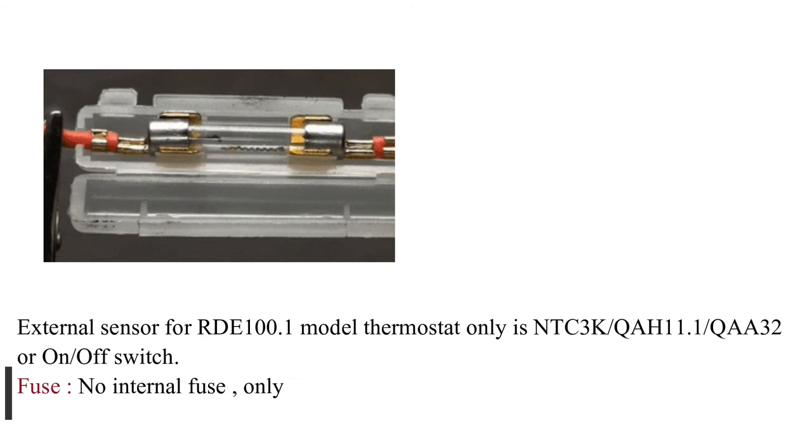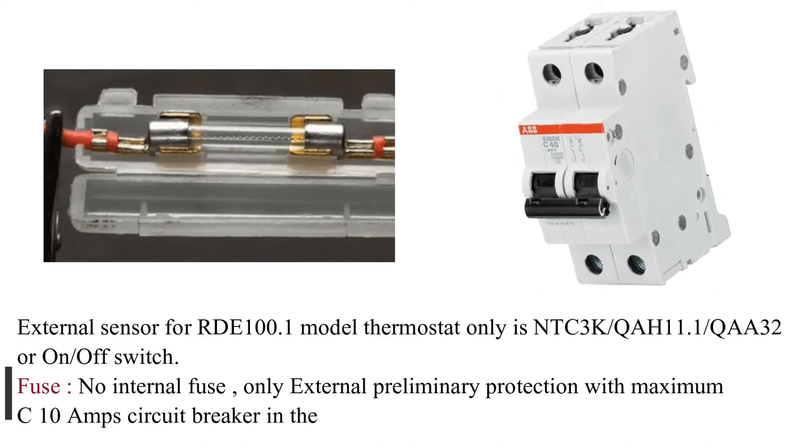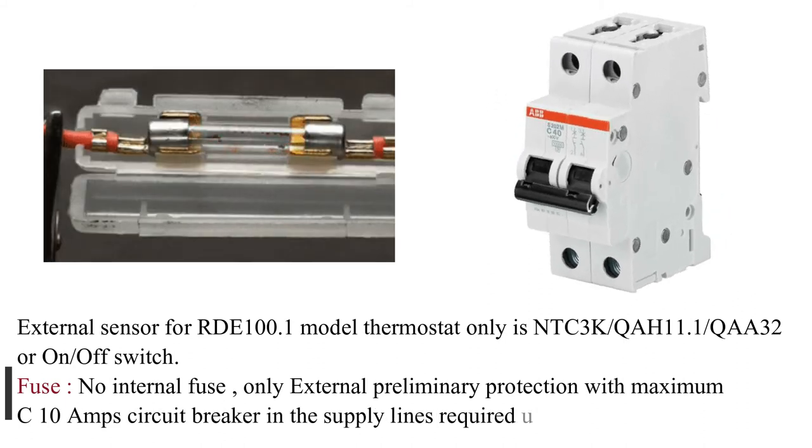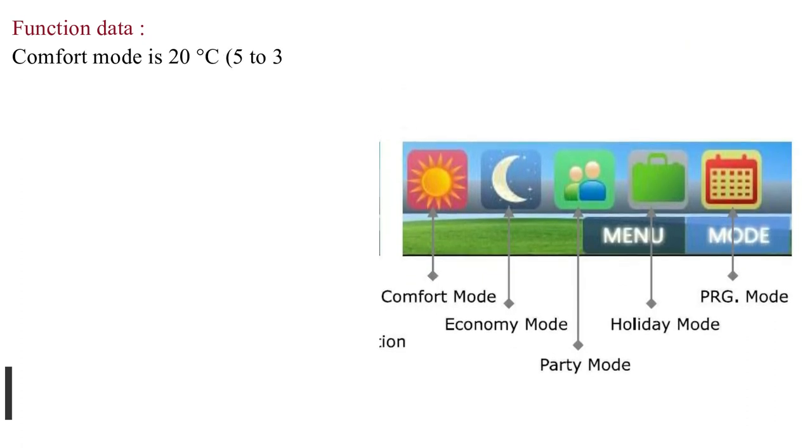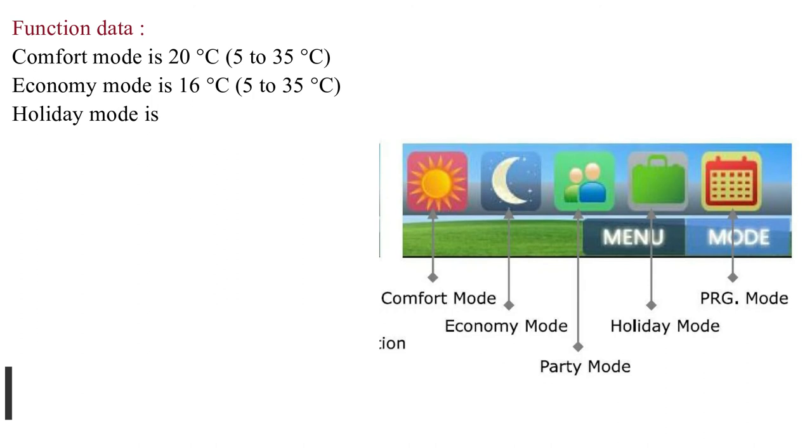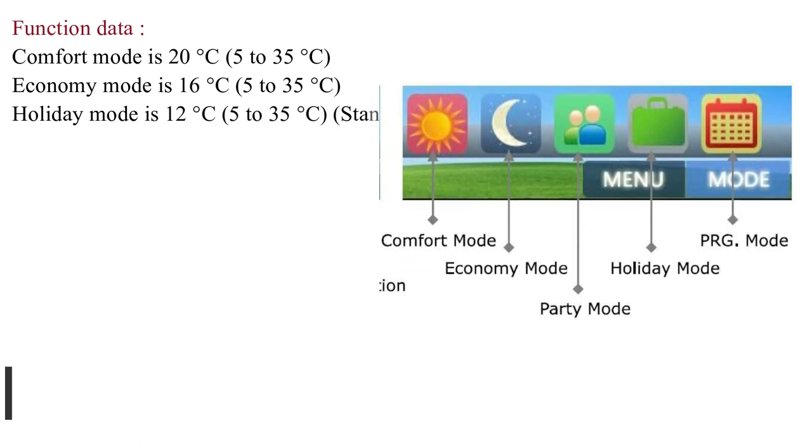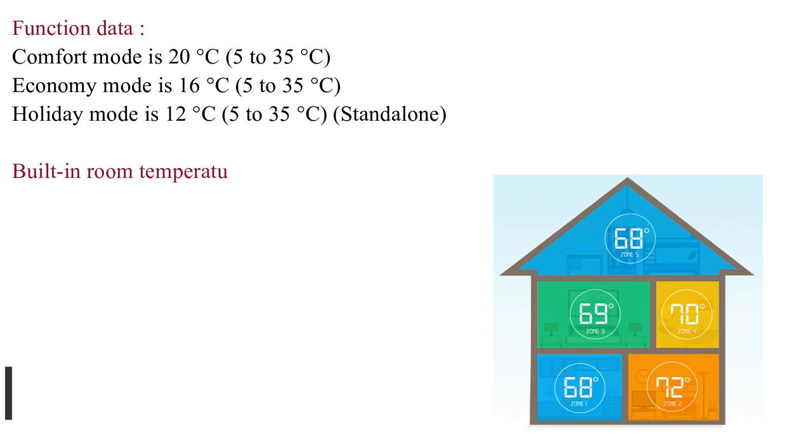Fuse: No internal fuse, only external preliminary protection with maximum C 10 amps circuit breaker in the supply lines required under all circumstances. Function data: Comfort mode is 20 degrees Celsius (5 to 35 degrees Celsius range), Economy mode is 16 degrees Celsius (5 to 35 degrees Celsius), Holiday mode is 12 degrees Celsius (5 to 35 degrees Celsius), stand alone.